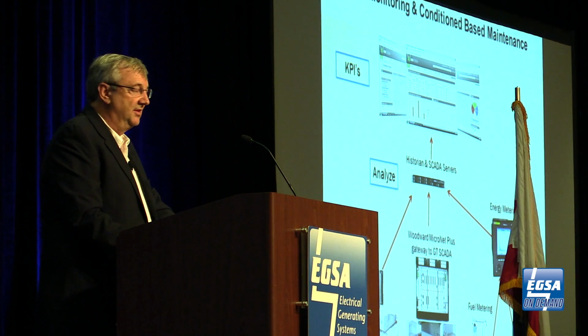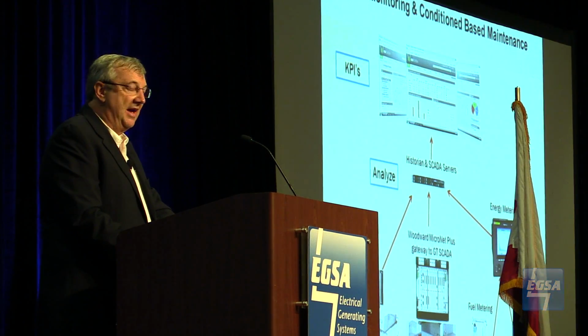When we talk about turbines, it's all about efficiency. We're burning massive amounts of fuel per minute on a 25 megawatt turbine. Looking at all the statistics off of that turbine, do we need to do what we call a water wash? You're pulling in massive amounts of airflow, even through air filters, trying to get that air as clean as possible before it hits the compressor, but it's still going to foul up. If it fouls up, it's going to affect your heat rate. You're burning more fuel to make the same amount of energy. Using statistics, we can analyze and say we need to take the turbine down, do a water wash on it, bring it back up, and now our fuel efficiency is back where it needs to be.